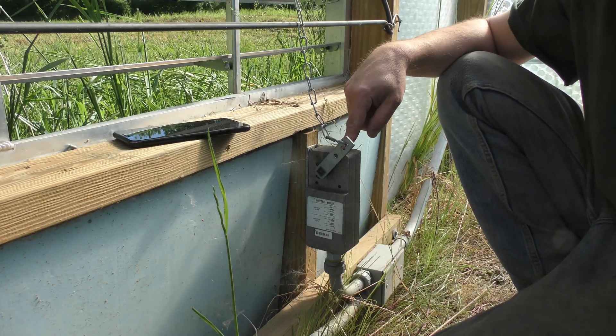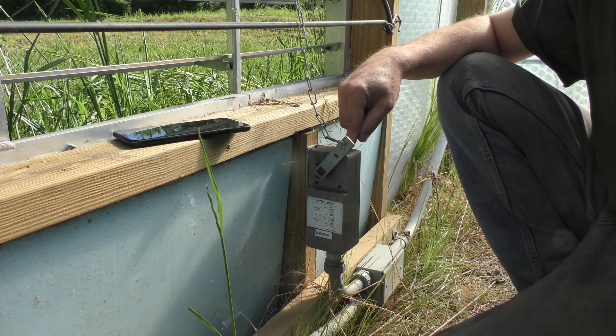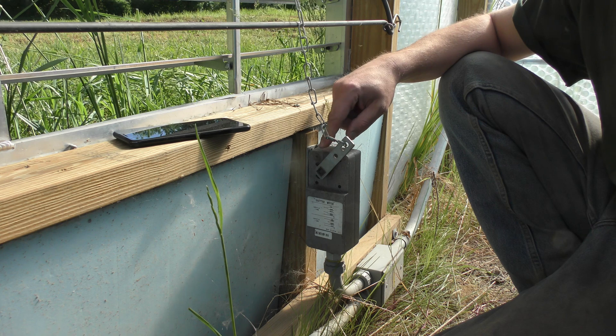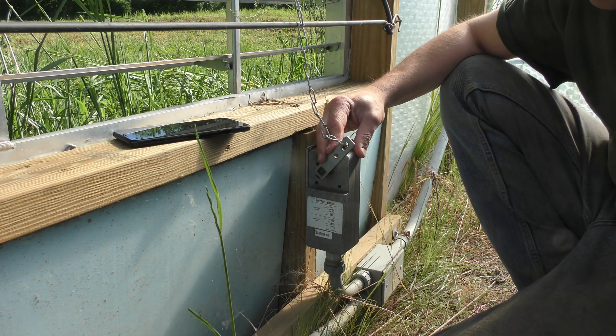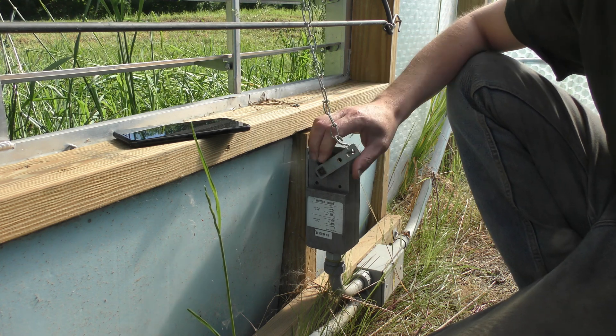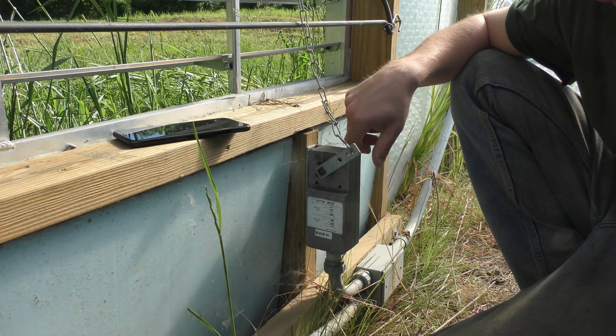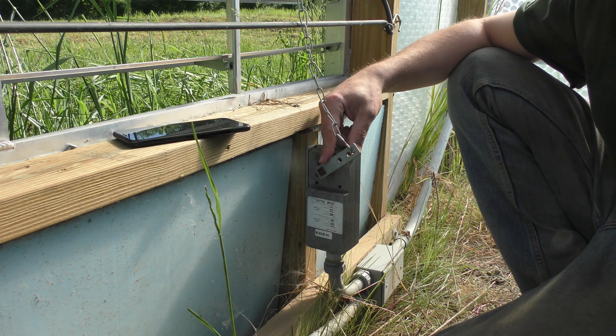I also have one unit that has failed, so the vent's still opening because of the second unit that's on there. But something inside has stripped, it's hot, and if you do push it a little bit, it'll eventually go. But it gets jammed up, so there's something broken with the gears or something jammed in it. It's a sealed case, so something's broken with the gears.